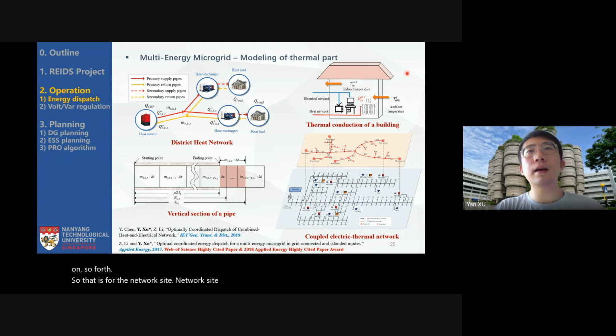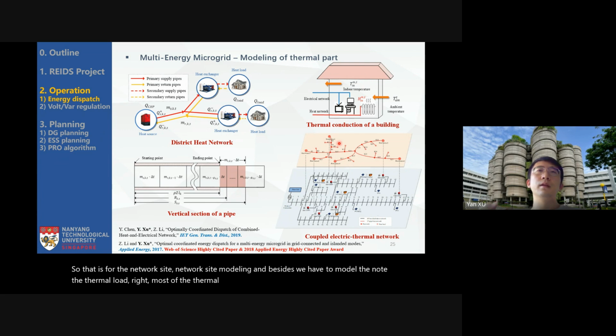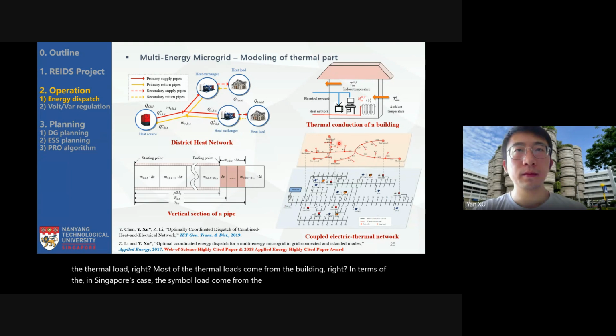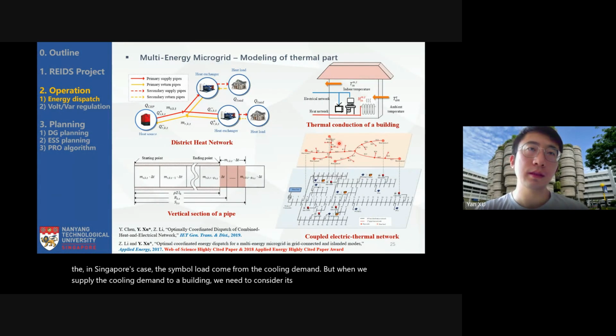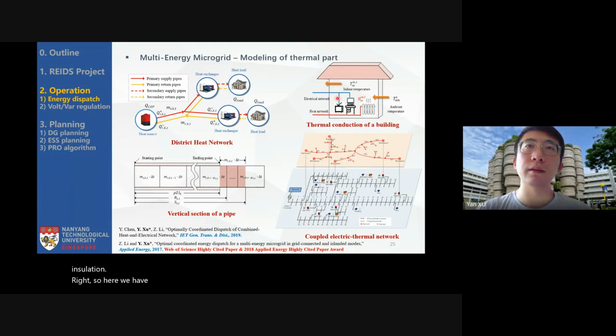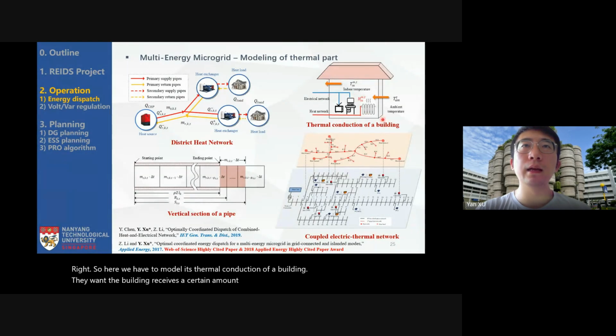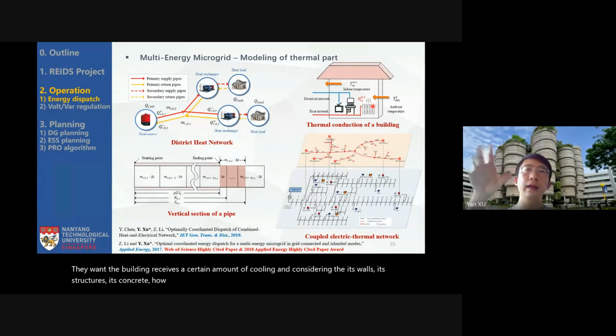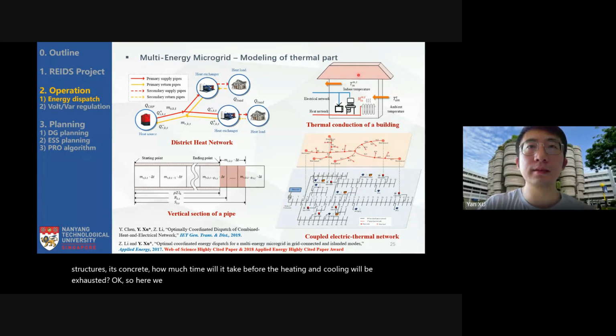Besides that, we have to model the thermal load. Most of the thermal load comes from the building. In Singapore's case, the thermal load comes from the cooling demand. When we supply cooling demand to a building, we need to consider its thermal insulation, so we model its thermal conduction. When the building receives a certain amount of cooling, considering its walls, structures, and concrete, how much time will it take before the heating and cooling is exhausted? So we have to consider the thermal model of a building at the load side.